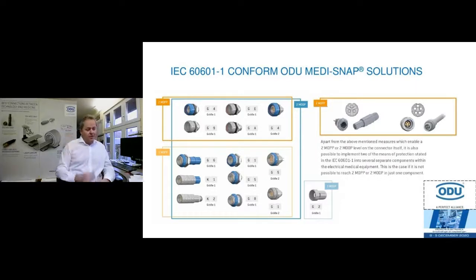And if you're thinking about my second slide with the picture of the operation room, this kind of receptacle you can use on all applications, on all monitors. This is safe for all applications. If you look down, you will find 8 other different receptacles, which have only 1 MOPP. Means there is only 1 MOPP, and you cannot use them in direct contact with the patient.